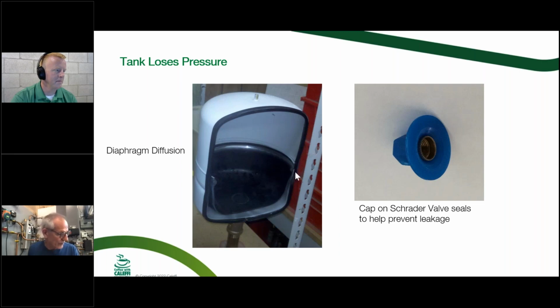And as I read through the manual here, they really don't want you pushing that diaphragm up much more than 50% of the way up the tank. Somebody can correct me if I'm wrong, because we don't want to stress that diaphragm. If you did push it up near the top of the tank, and somebody underpressurized the air side or put more water in, then number one, you're going to stretch that diaphragm, but you can also reduce the acceptance volume of the tank because your air bubble's been squished up in there. So two things, and we'll talk about that on chilled water and solar. There are some instances where you might want to overcharge your tank a little bit, which I think is coming up, to give you a little reservoir.